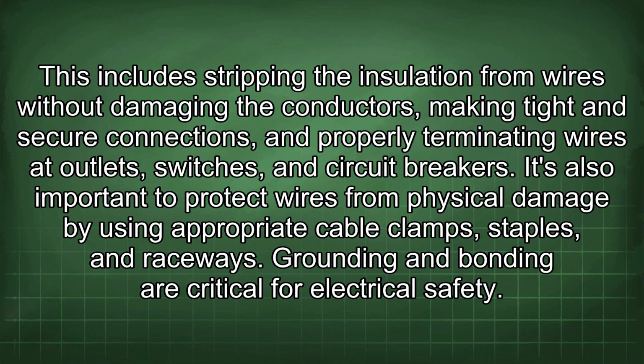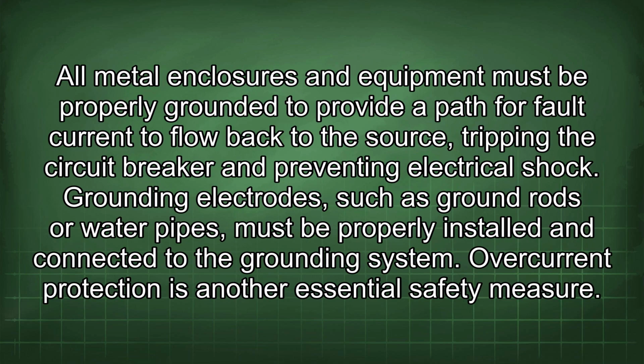Grounding and bonding are critical for electrical safety. All metal enclosures and equipment must be properly grounded to provide a path for fault current to flow back to the source, tripping the circuit breaker and preventing electrical shock. Grounding electrodes, such as ground rods or water pipes, must be properly installed and connected to the grounding system.